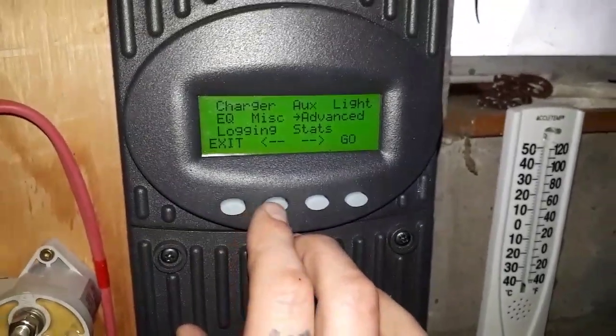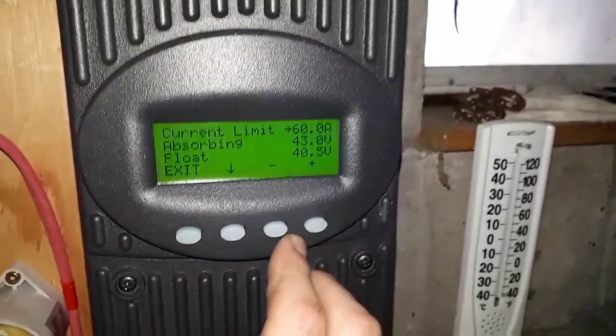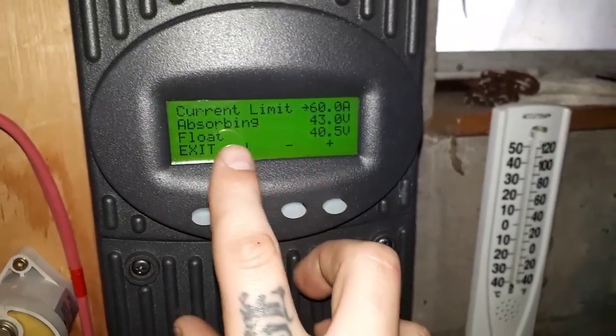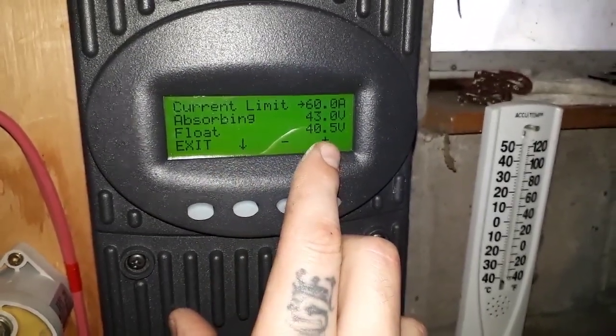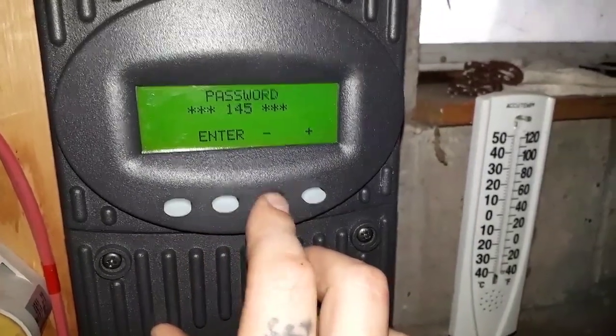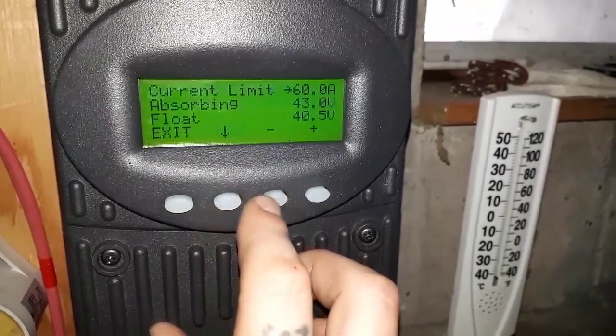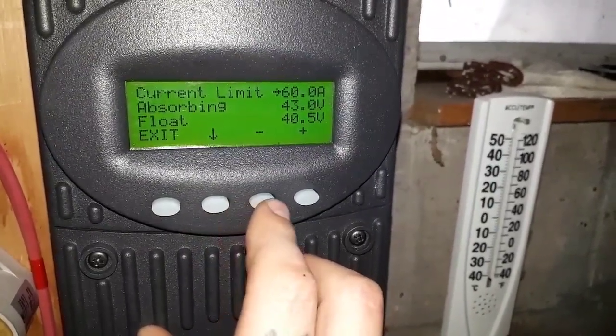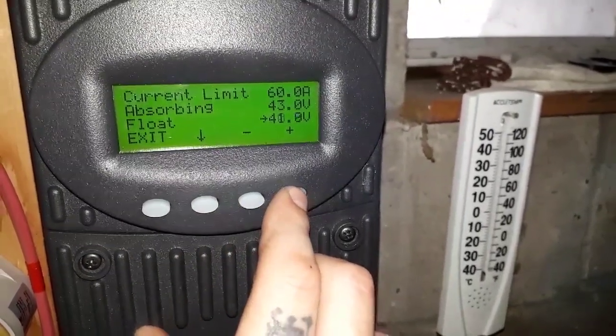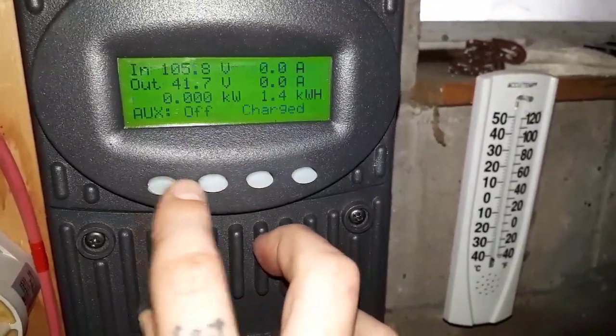I've already got my absorb voltage set to 43, like I had on the display there. My float voltage is going to be reset. The standard password is 141 on every controller. I'm going to go to flex maxes and go down to the float setting. I'll increase this to 40.5, then exit that.